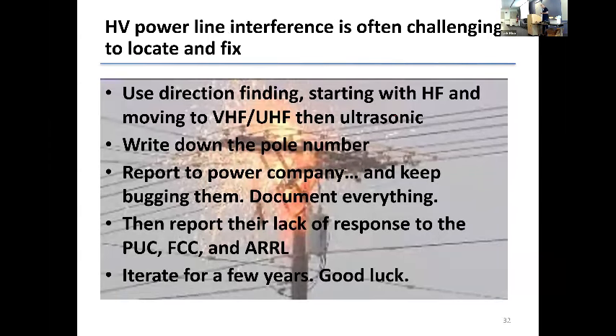High voltage power lines. It's never the transformer, by the way. There's a transformer there, but it's not the transformer that's the problem. It's always an insulator or a bad connection. Loose hardware is very common, since weather and that kind of stuff loosens hardware over time, and you get arcing, which may come and go with the weather, especially with rain.